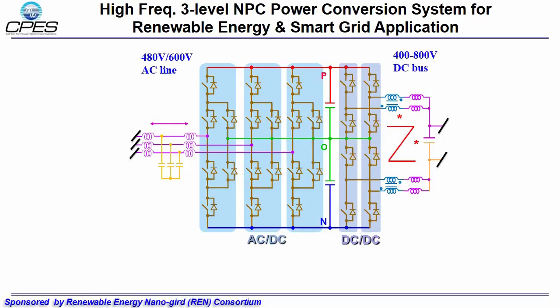The AC side is connected to a 480 volt or 600 volt utility grid, and the DC side can be connected to 400 to 800 volt DC bus. The AC and DC side is decoupled by this 1200 volt DC link. The whole system has 200 kVA power rating with 20 kHz switching frequency. It has a bidirectional power flow with 4-quadrant operation capability.